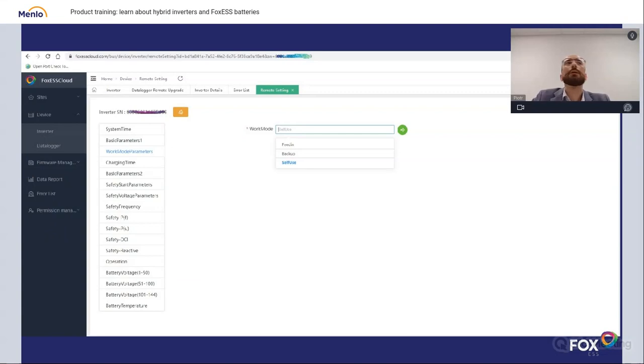Voltage parameters, of course, can be changed, but it's not recommended by the producer, by the manufacturer. But in some cases, there is a strong concern. If the lines are very long from the inverter to the client, the voltage drop on those lines may be compensated by giving 2 volts, 3 volts of such compensation for your device. So you may always trim this unit to your needs on site, really easy.